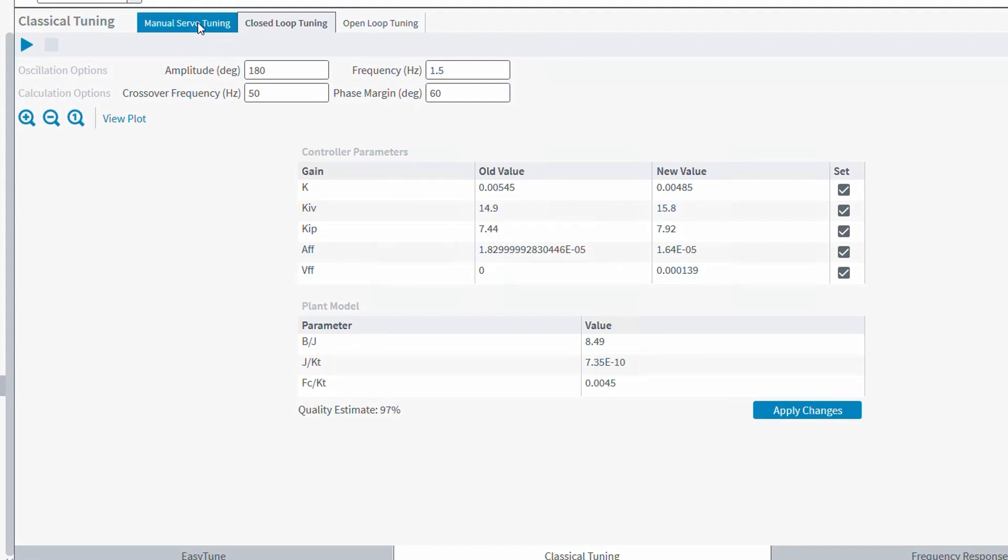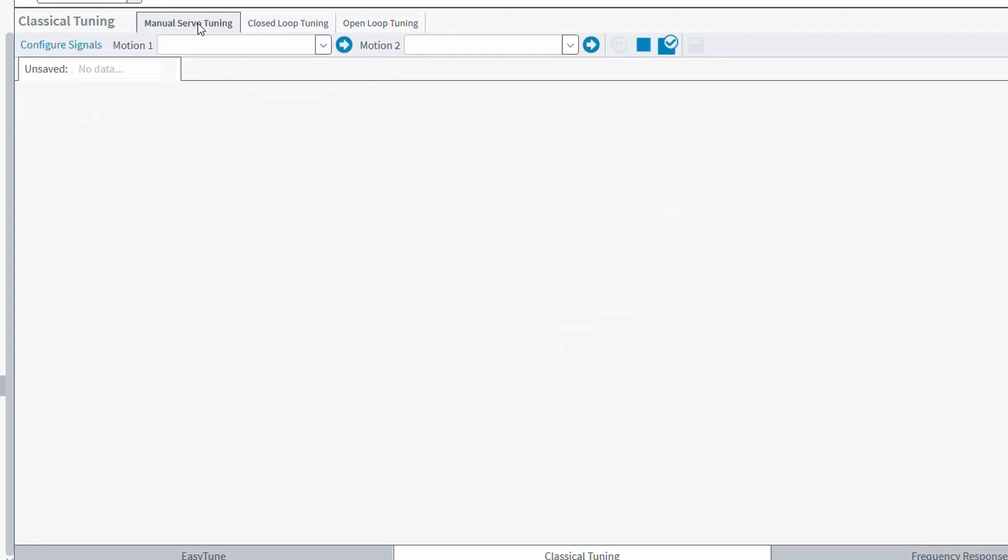And finally, we have the manual servo tuning. This allows the user to input a move, execute that move, and then based on the output response, make adjustments to the servo loop gains. Because this is done by making moves and adjusting the gains, then repeating the process, this tuning method is often used when you're trying to optimize for a particular move that is made over and over again.